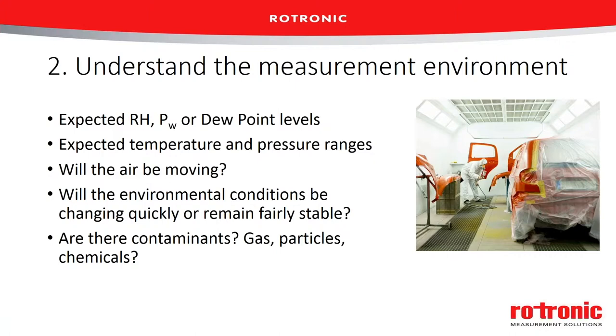It's important to understand the conditions under which you're going to measure. What's the expected relative humidity range? You'll need quite a different instrument if you're measuring in office environments with ambient conditions versus a high-temperature, high-RH chamber or a dry box. You need to understand the full range of relative humidity expected. Same thing with water activity or the actual mass of water vapor — what is your expected range? If measuring dew point, what level are you expecting? It's much easier to calculate dew point above 10% RH than below 5% RH.